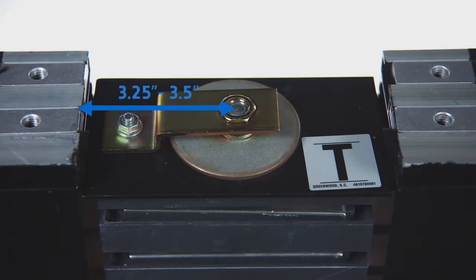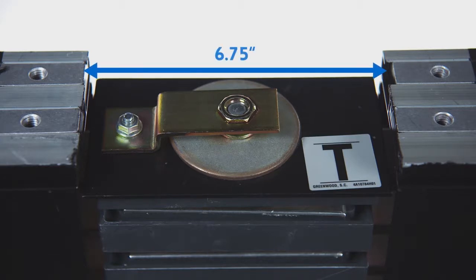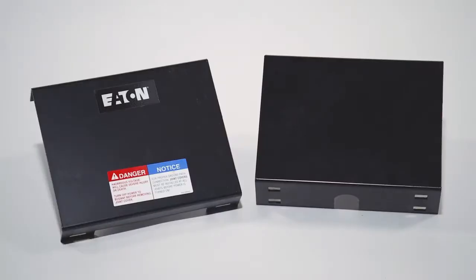Slide the conductor end into the bridge joint until there are 3 1/4 to 3 1/2 inches from the edge of the housing to the center of the smart bolt. To match the dimensions shown on the customer layout drawing, the distance between the edges of the housings should be approximately 6 3/4 inches. After both sections of busway are connected, you can install the joint covers.